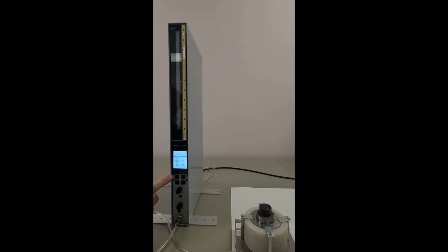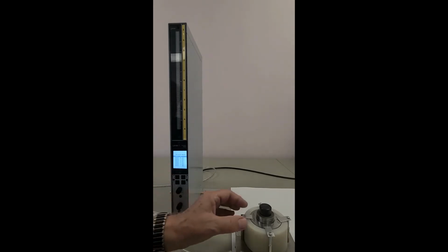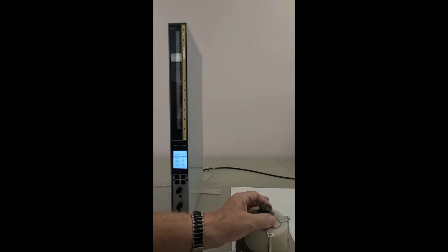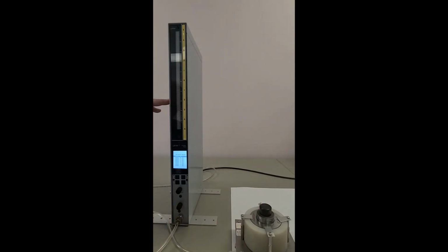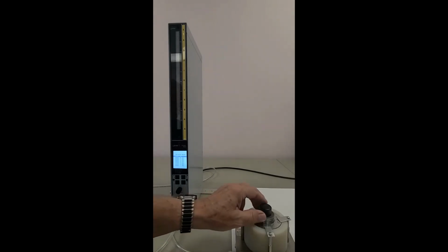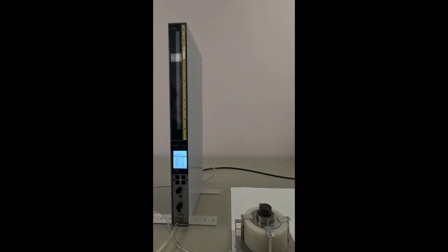We go into that. It allows you to set a reset time, and this is particularly useful for automated conditions. For example, if I select a reset of 4 seconds, when an operator is inserting a part into a fixture and turns it, and he lifts that part out of the fixture to put the next one in, that will typically cause the display to peak. The column will recognize that a part has been removed and it will start this reset time. So the operator would have 4 seconds to take the part out and put the next part in before it actually performs the reset.